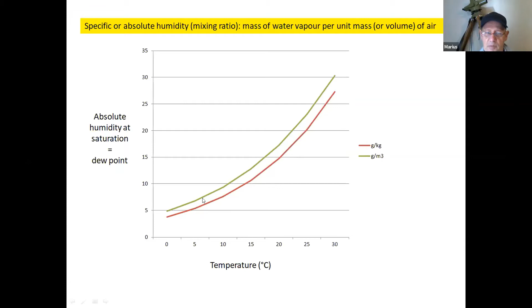In other words, when it's totally saturated, 100% relative humidity, which would by definition be the dew point, you can see the green line represents the grams of water per cubic meter of air, and the red line represents the grams of water per kilogram of air. And they follow the same pattern. And basically what we see is as you increase the temperature from 0 up to 30, there's an exponential increase in the amount of moisture that's held either per kilogram of air or per cubic meter of air. And this is a very important factor because it's an exponential increase.